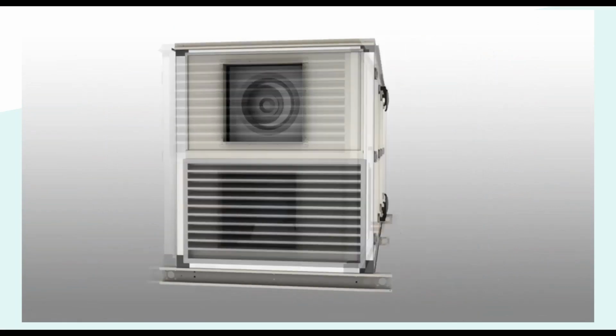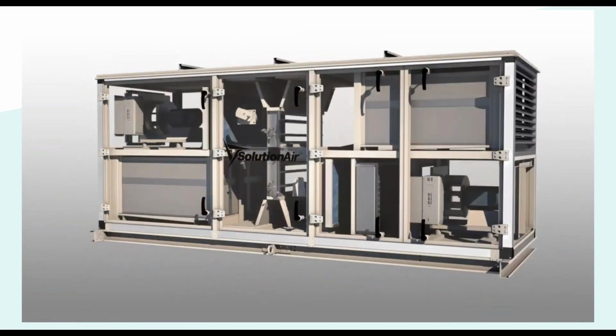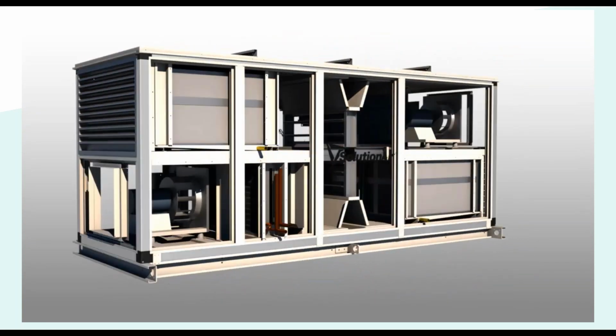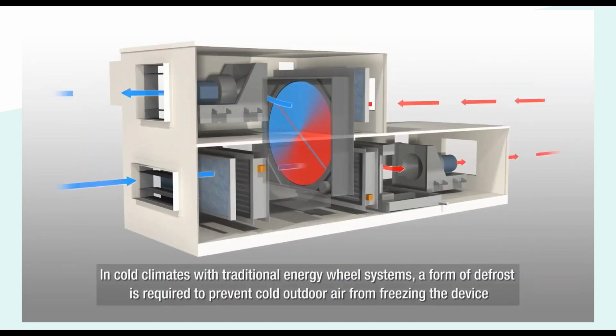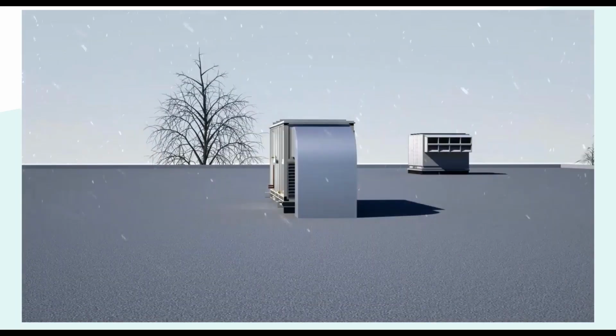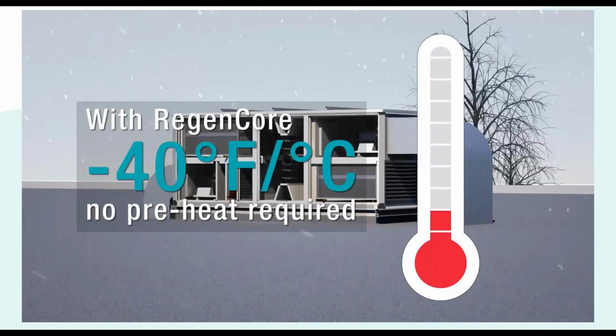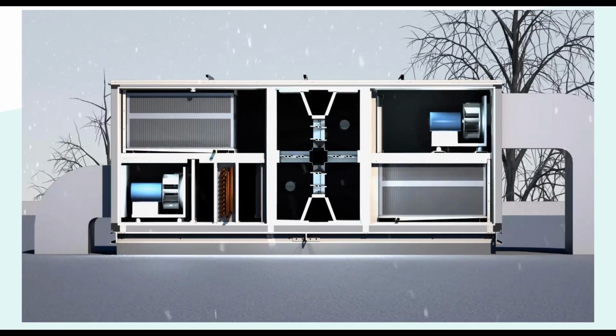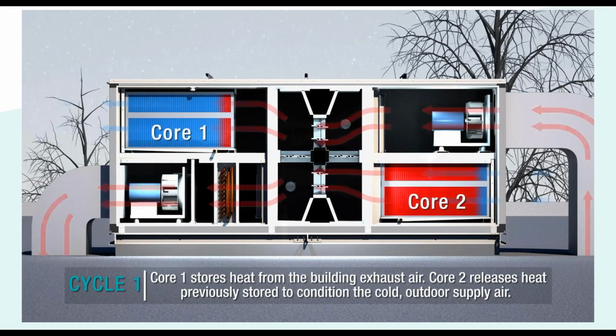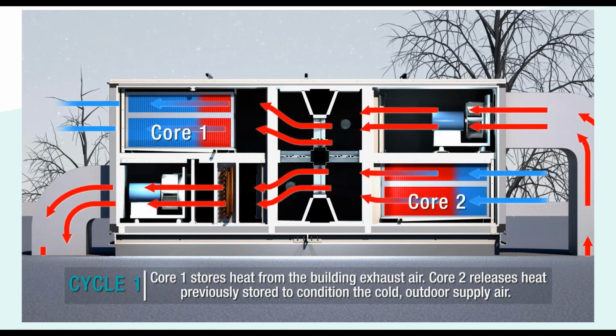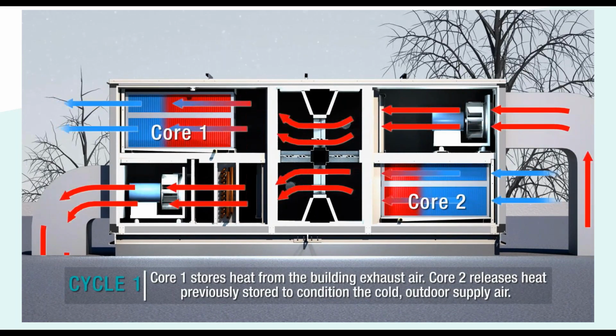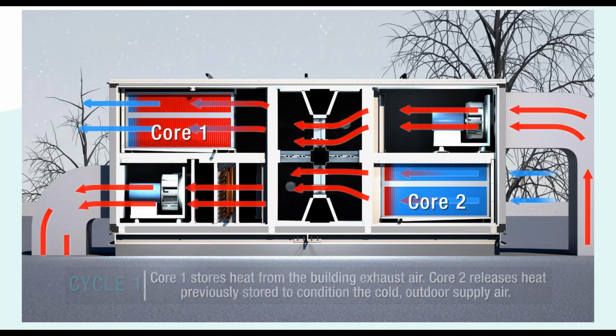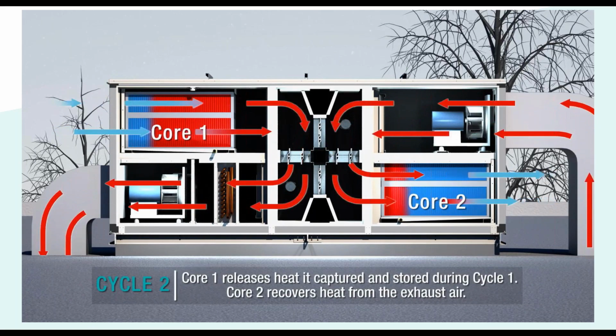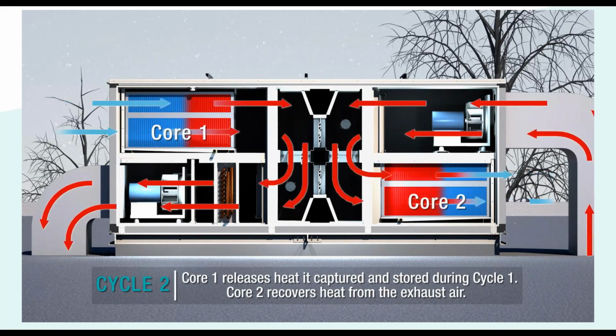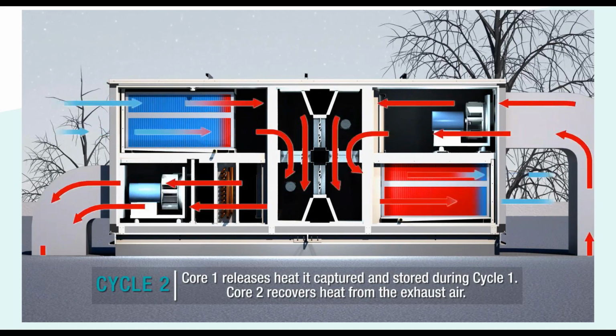RegenCore is a high-effectiveness energy recovery unit, recovering sensible and latent energy during both heating and cooling seasons. In cold climates with traditional energy wheel systems, a form of defrost is needed to prevent cold outdoor air from freezing the device. With RegenCore, no preheat is required, down to outdoor air temperatures of minus 40 degrees Celsius. During the first cycle, Core 1 stores heat from the building exhaust air, while Core 2 releases heat previously stored to condition the cold outdoor supply air. In cycle 2, the dampers are repositioned, allowing Core 1 to release the heat it captured and stored during cycle 1, and Core 2 recovers heat from the exhaust air.